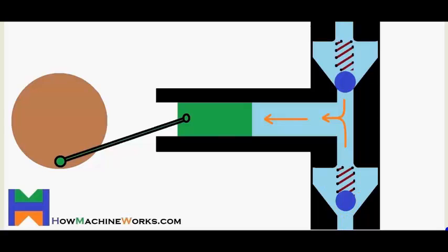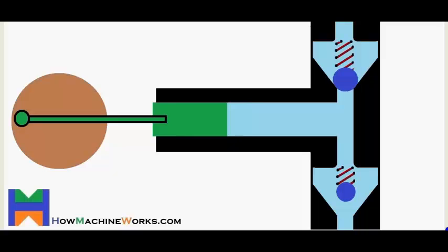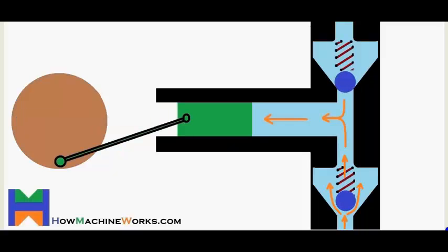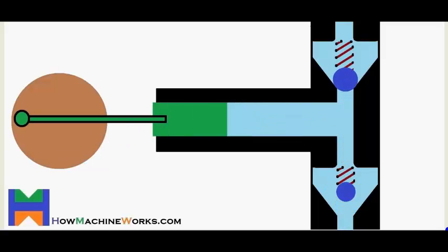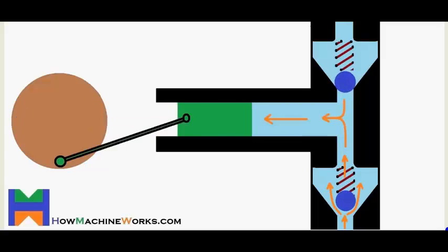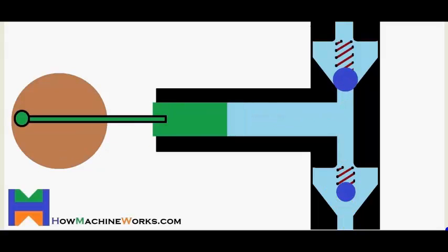The inlet valve opens up and oil enters through the inlet valve, and that's carried into the body of the plunger pump itself. So that gets into the body of the plunger pump, but the outlet valve will be closed. Now further the rotor rotates and the plunger moves backwards again, and the low pressure and the suction further increase, so more oil is getting inside the plunger pump. At this time the outlet is firmly closed, but the suction is happening.